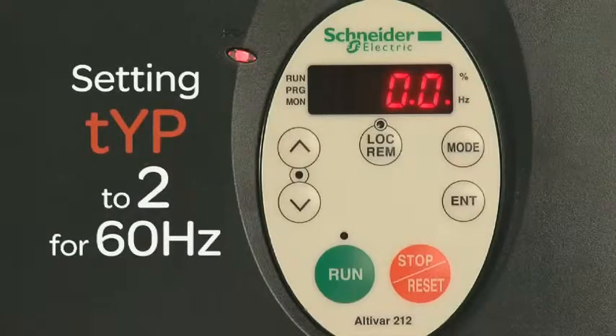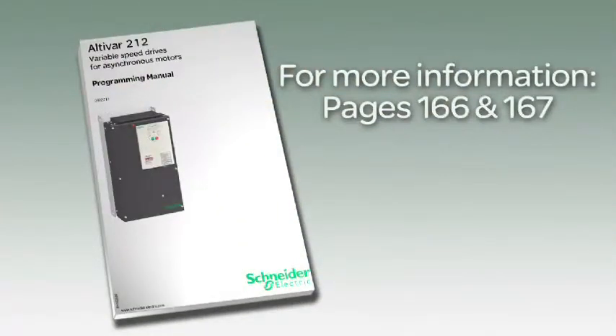Setting the TYP parameter to 2 sets specific parameters to values suitable for 60 Hz incoming frequency. For more information, see the table on pages 166 and 167 of the Altivar 212 programming manual for a list of parameters that are affected by this reset action and their resultant values.